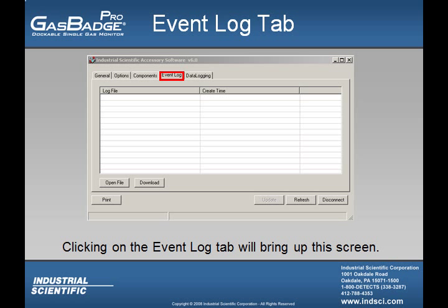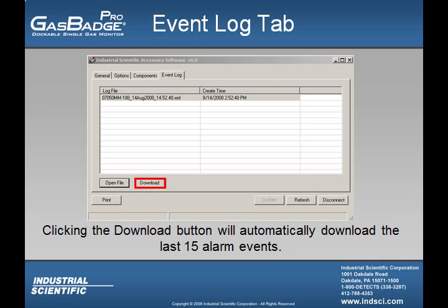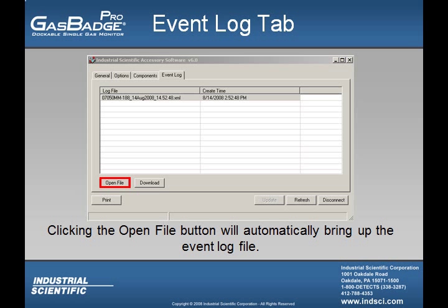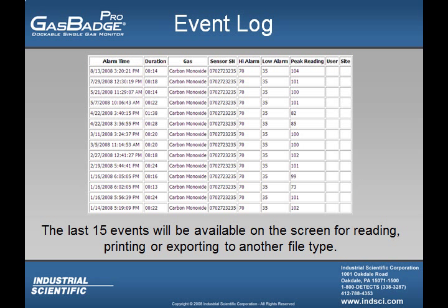If the user wants to check the event log stored in the instrument, they can click on the Event Log tab. After clicking on it, the user will want to click the Download button, and the Datalink will load the last 15 alarm events stored inside the instrument. Once the user clicks on the Open File tab, the Datalink software will automatically load the entire Event Log file. From this screen, the user can view the alarms, print the alarms, or export the alarms to another file type.